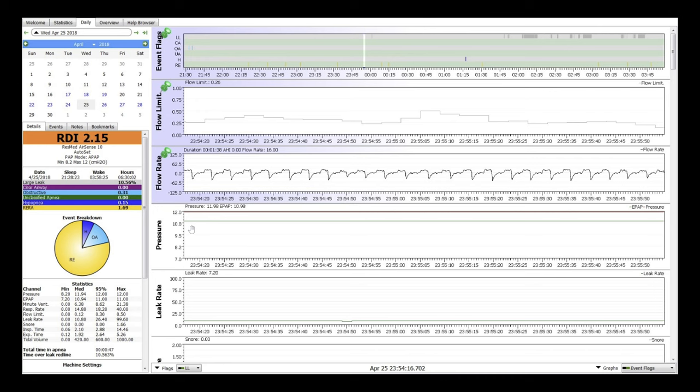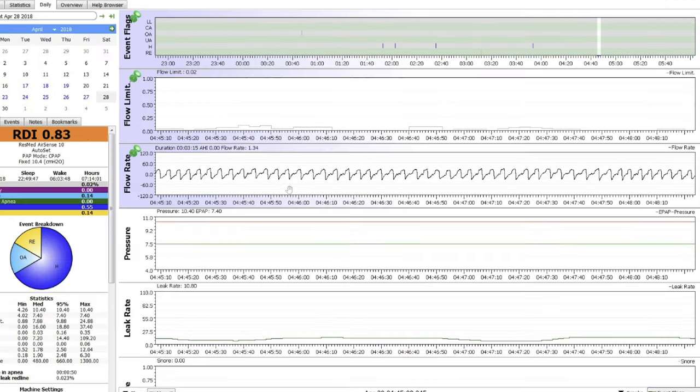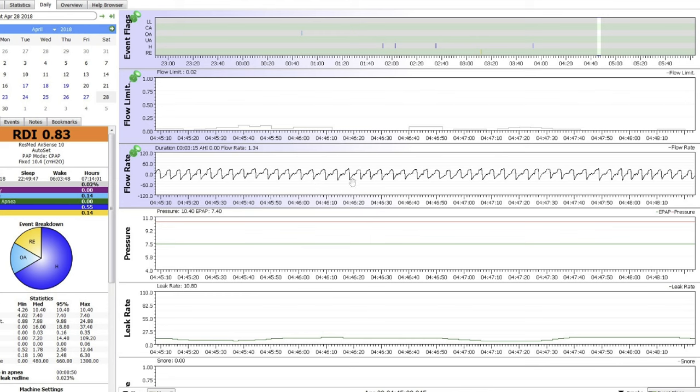So here's another one. This is courtesy of apneaboard.com. You can see that these breaths are very flat and have considerable amounts of flow limitation, which are quantified up here in this line. That's with EPR on zero or one. And then in the next one, they turn EPR up to three. And here, same patient, but EPR on three. You can see that the flow limit is drastically reduced. And you can see that the waveforms of these breaths are much more normal and much more aligned with what we want to see.